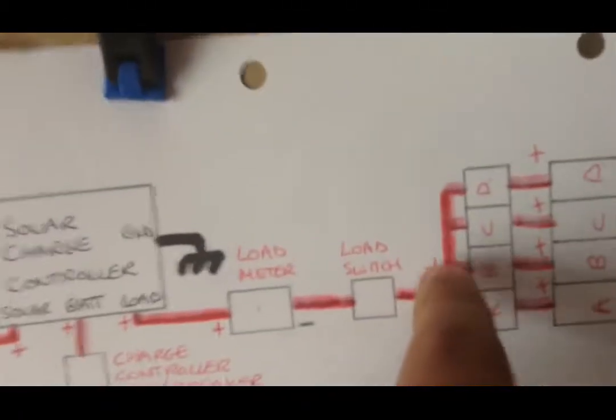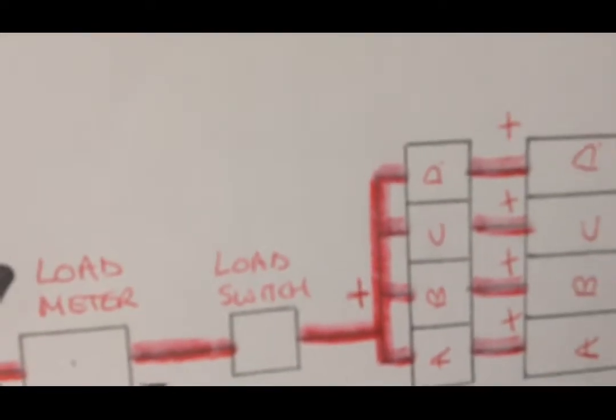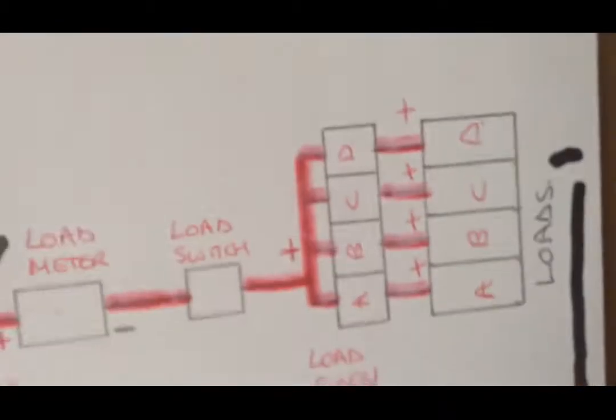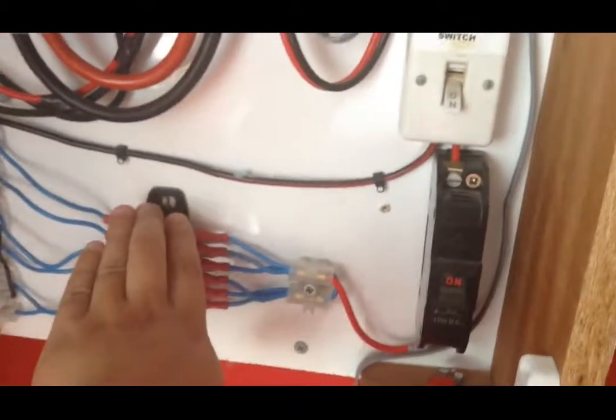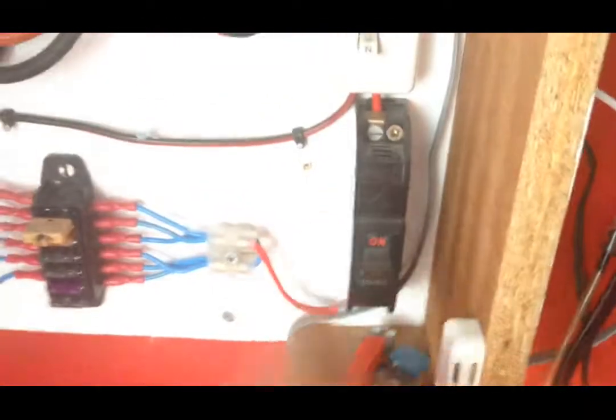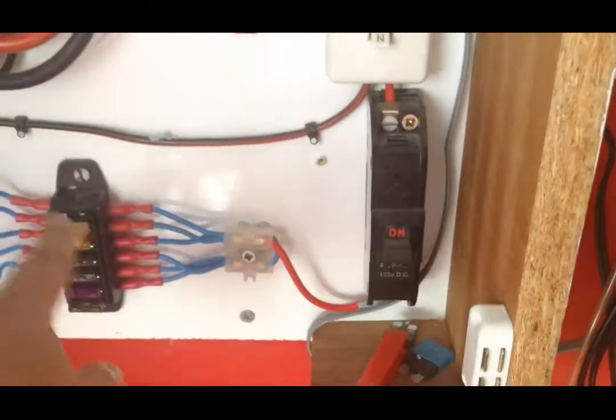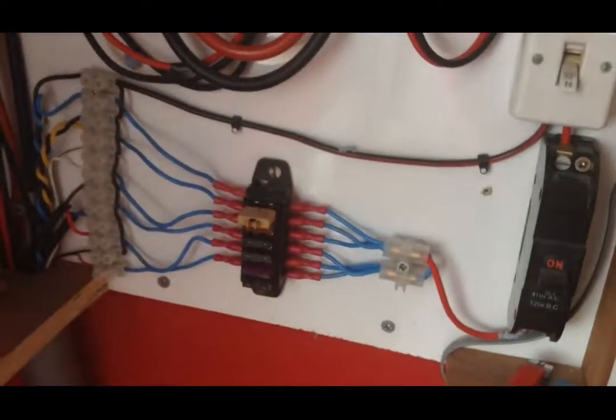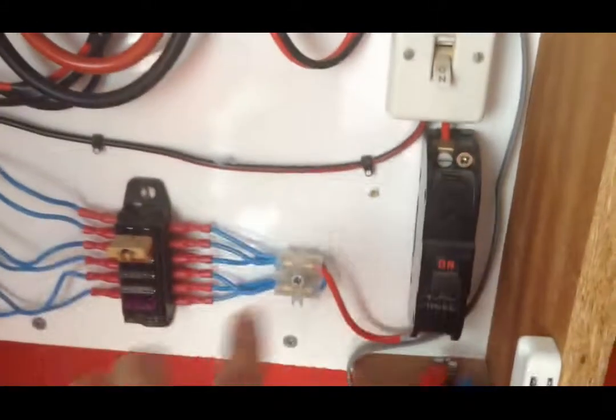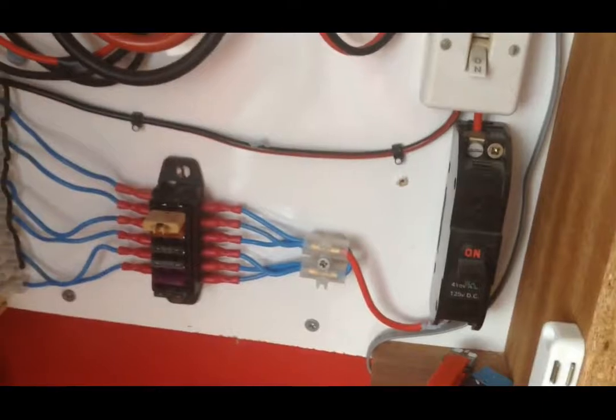So fuses go in all the positive lines towards the battery, so the battery is in this direction, pointing this way. So you put fuses in all the positive wires. Now, if you use a separate fuse for each load, if one load goes faulty, all your others will carry on working. Whereas if you wire everything to one breaker, say I did not have a fuse board here, and everything here was wired to this breaker, and this is a 5 amp breaker, so if something on this side went wrong and it drew more than 5 amps, it would trip this out, but it will cut off the power to all my loads, not just the thing that went faulty. So that could be a pain.